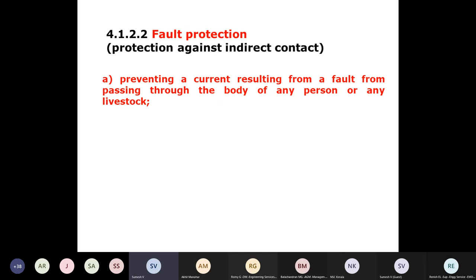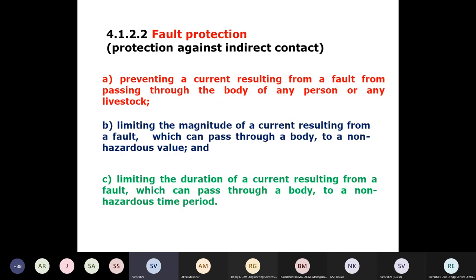Then, so far we have discussed protection, safety from certain incidents. Now, fault protection. When a fault occurs, that fault is to be cleared. For that, some protection equipment is to be provided. What is fault protection? 4.1.2.2 says: A, preventing a current resulting from a fault from passing through the body of any person or any livestock. B says that limiting the magnitude of current resulting from a fault which can pass through a body to a non-hazardous value. C states that limiting the duration of the current resulting from a fault which can pass through the body to a non-hazardous time period. That is, if the magnitude of the current and the time period are limited, we can ensure protection.